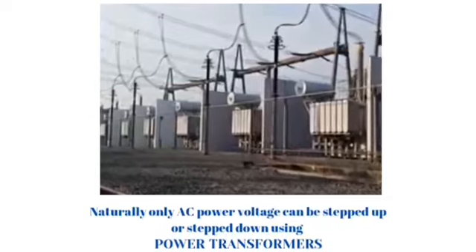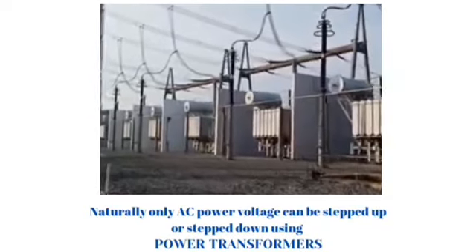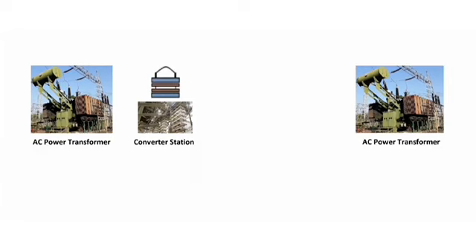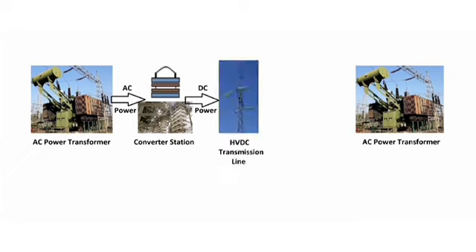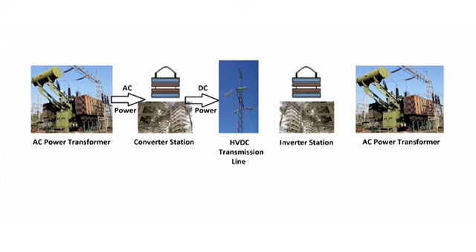Naturally, only AC power voltage can be stepped up or stepped down using power transformers. Hence, for HVDC transmission, we have normal HVAC power transformers at both ends. Then there is a converter station at the sending end of the line, which converts stepped up AC power into DC power. This DC power is transmitted over the distance by DC transmission lines. At the receiving end, there is an inverter station which converts DC power back into AC power, which again can be stepped up or stepped down as per requirement using power transformers.